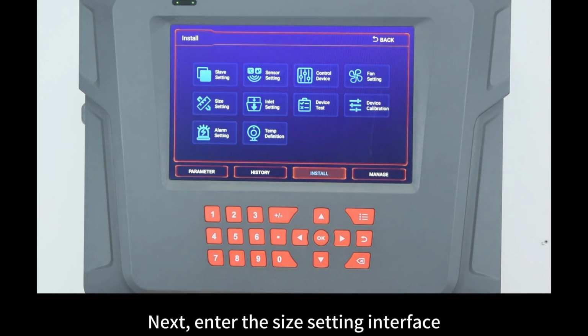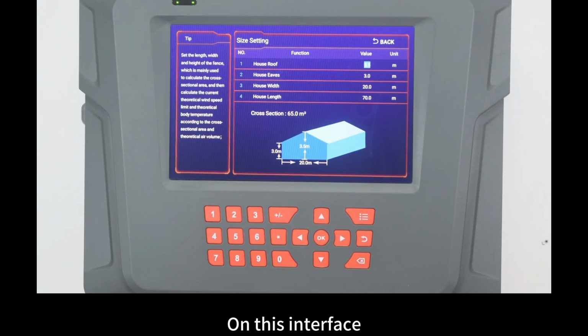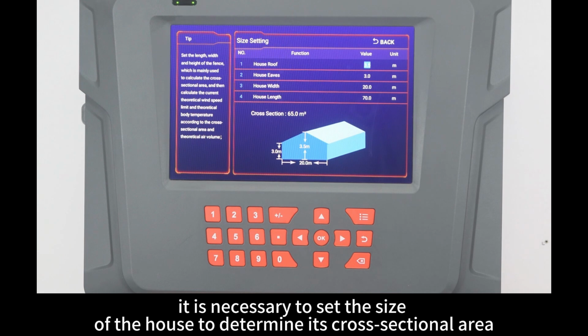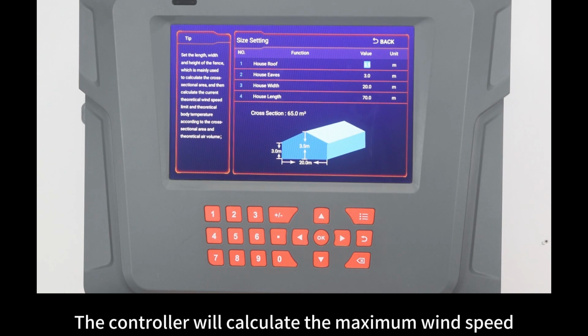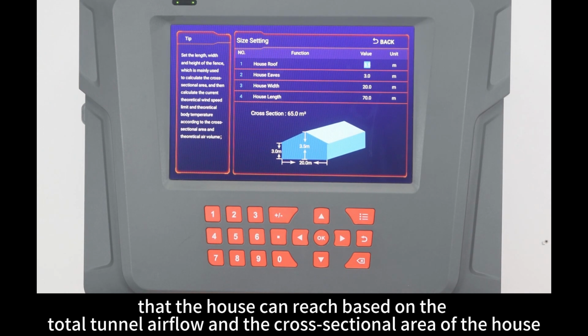Next, enter the size setting interface. On this interface, it is necessary to set the size of the house to determine its cross-sectional area. The controller will calculate the maximum wind speed that the house can reach based on the total tunnel airflow and the cross-sectional area of the house.